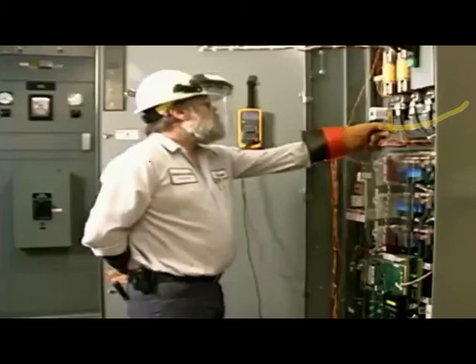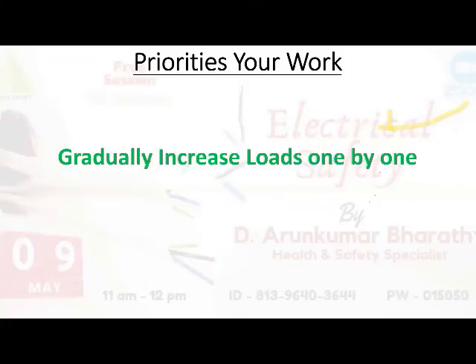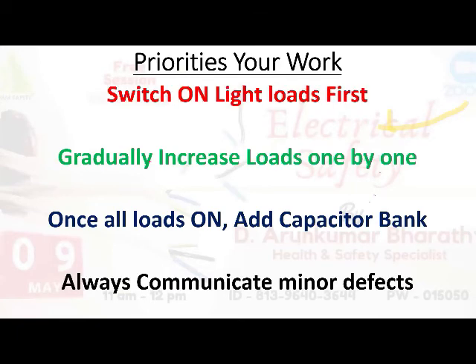These are fundamental but very important practices. Now coming to the operation part: first always switch on the lighting loads. Then gradually increase the load one by one. For each load you switch on, check whether the tripper is working or whether you hear any noise warning. The noise warning may mean the earthing is not proper, there is a leak of electricity, or there may be some loose connection.